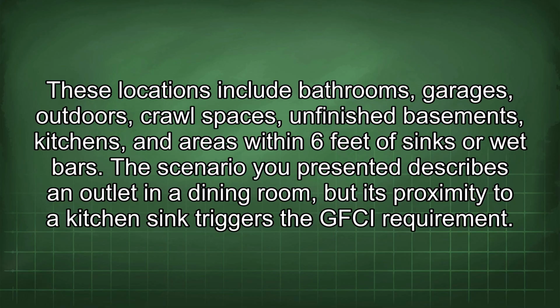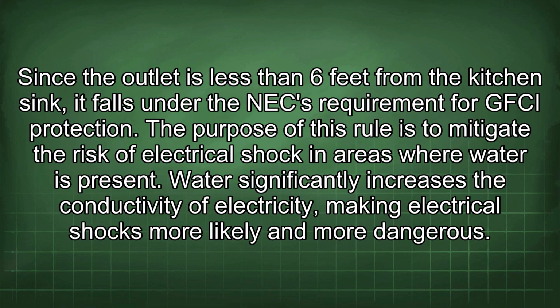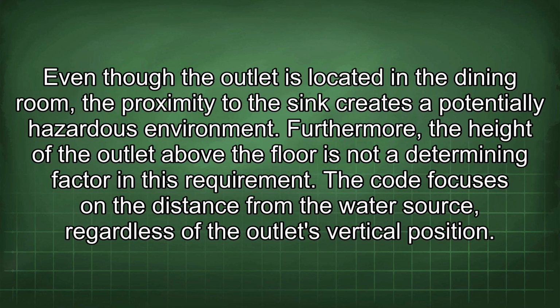bars. The scenario you presented describes an outlet in a dining room, but its proximity to a kitchen sink triggers the GFCI requirement. Since the outlet is less than 6 feet from the kitchen sink, it falls under the NEC requirement for GFCI protection. The purpose of this rule is to mitigate the risk of electrical shock in areas where water is present. Water significantly increases the conductivity of electricity, making electrical shocks more likely and more dangerous. Even though the outlet is located in the dining room, the proximity to the sink creates a potentially hazardous environment.